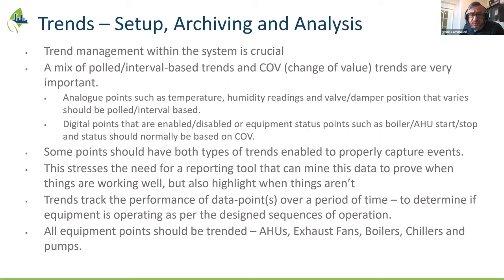It's good that we talked about trends and the importance of archiving them over a long period of time so you can see if equipment is operating as per the sequences of operation. From personal firsthand experience, 99% of the time a BAS provider will go in and program it, but if they don't have a verification process—and many don't, that's just the reality—they don't use trend logs. But demand that they do. When you get sequences of operation that indicate they've been implemented, ask for proof—show me through trends that it's actually working as intended. That's something I heard Adam say and Dave harp on as well, so it's important to keep in mind.